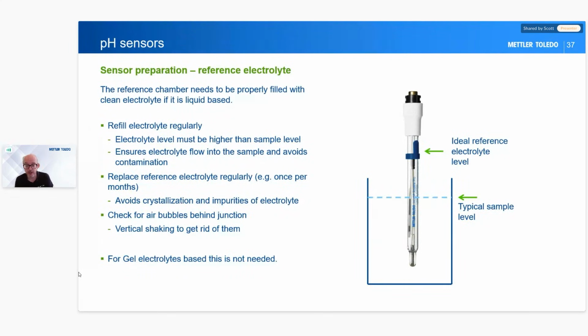However, if we're using a liquid electrolyte, then we will need to empty and clean that electrolyte on a regular basis. So what we must do is empty and refill that electrode. We're not topping the electrode up with some new electrolyte, we need to empty it. The reason is that when we start, we use 3 molar potassium chloride. If it evaporates or crystallizes inside, it becomes 4 or 5 molar. Then we top it up with 3 molar, so it becomes 4 molar, and then it goes up again to 6, and then we top it up again. Basically what we're doing is hypersaturating that solution with potassium chloride.